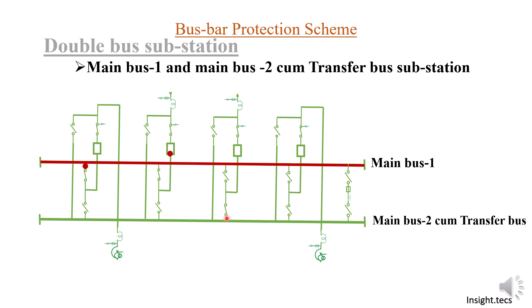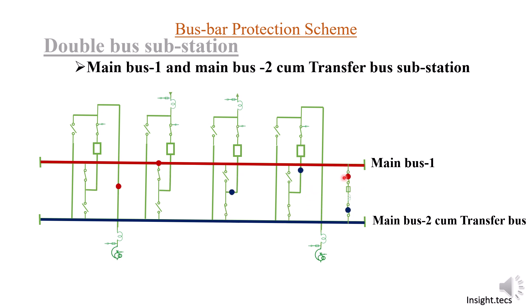When the second equipment is connected to main bus two, the power flow charges bus two. Similarly, bus two being charged allows transformer two to also get charged once the bus coupler and the two isolators are connected. At that point, power flow between bus one and bus two is occurring and both will be at the same voltage level.